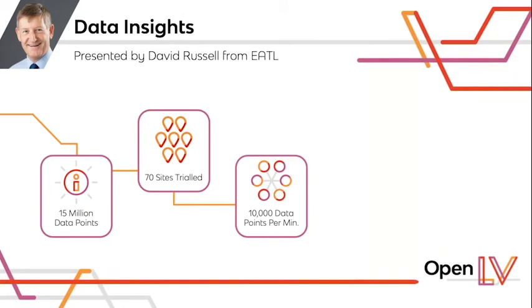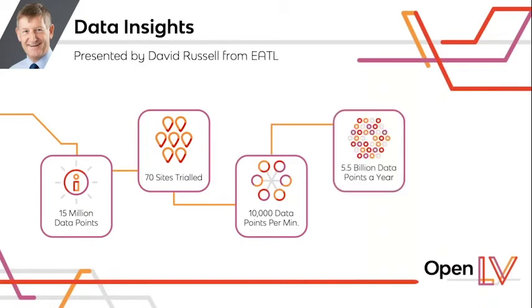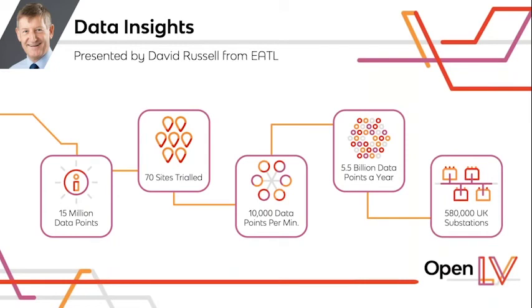And while few will debate the need for greater visibility and control of the LV distribution network in order to help the UK achieve its net zero targets, I guess these huge numbers explain the vast quantities of data that would be involved in this undertaking. And the OpenLV project has shown that distributed intelligence can help mitigate this data issue. By local processing, it can reduce the costs involved with transmitting data by reducing the amount of data that needs transmitting. Using exception reporting to direct central controllers to issues at particular substations as they occur, and implementing local control of the distribution network, it can enable staff to prioritize actions and focus at the higher voltage levels.